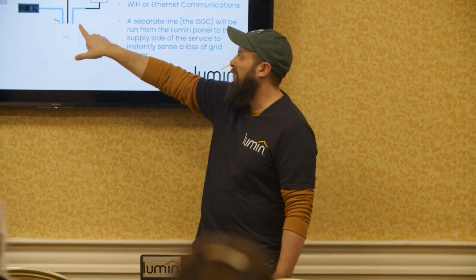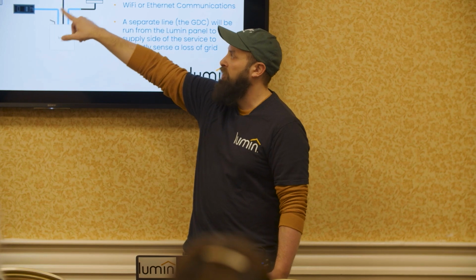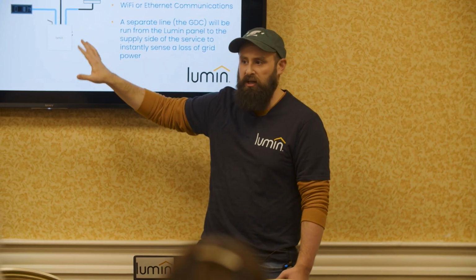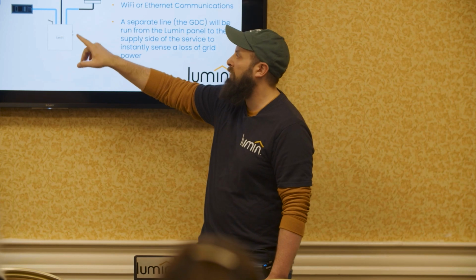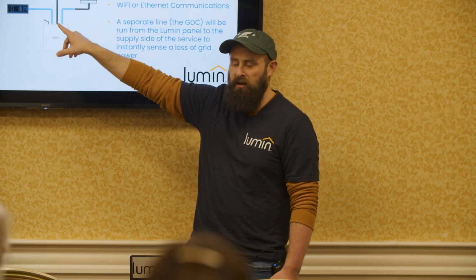Part of that agnosticism means that we need to get all of our own metrics by ourselves. And so the way in which we recognize a grid outage is to actually reach a reference outside of the backup system. We are taking a conductor and attaching it in a whole home backup. Of course, this is different for a partial home backup. But in a whole home backup, we're taking a conductor and attaching it to the supply side as a voltage reference. As soon as that voltage goes from 120 to 0, we recognize a grid outage has occurred, and we go into our load shedding protocols.